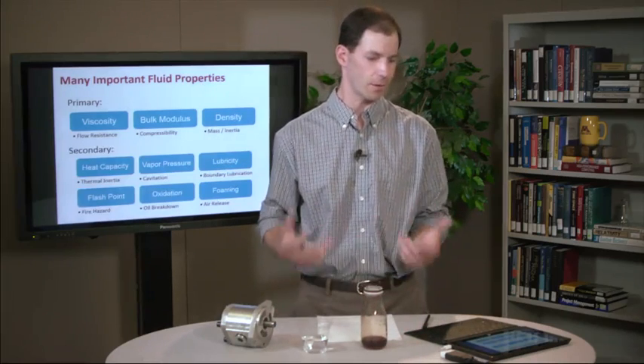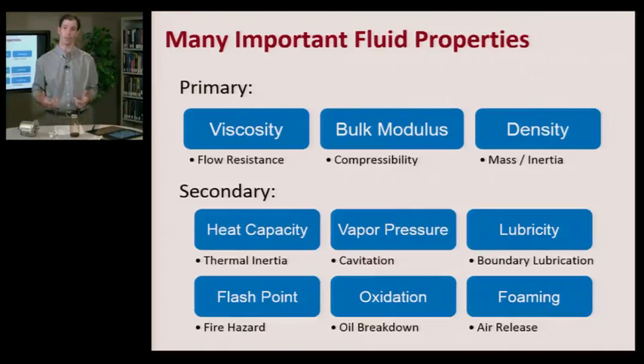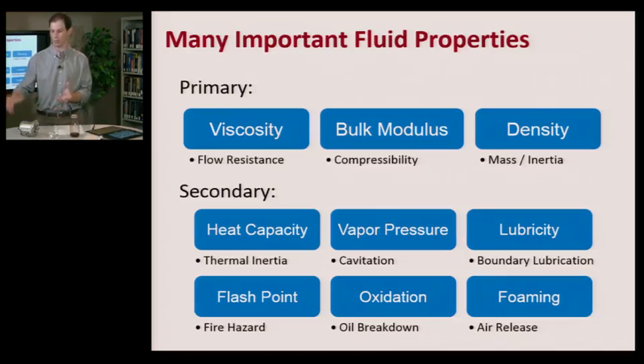Some secondary fluid properties that we need to pay attention to: heat capacity - how much heat can we carry with the fluid? What's the vapor pressure of the fluid? The reason that this is important is because normally we have an atmospheric pressure in our reservoir and then as we're intaking fluid into a pump often that pressure drops, and if the pressure drops below the vapor pressure then we're going to get the oil turning into a vapor.